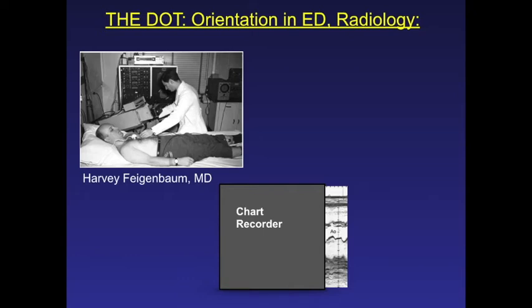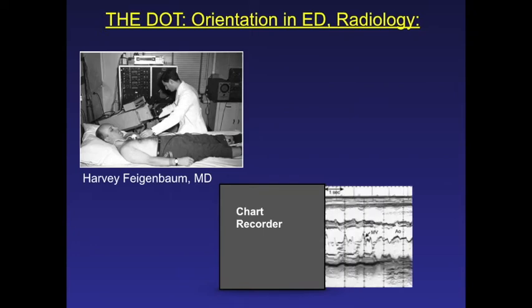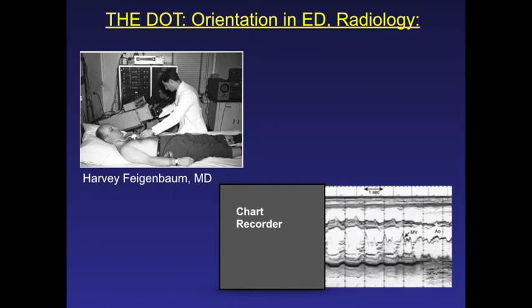Now, an M mode of the heart is one single beam, one scan line from one crystal on a transducer. And what they had to do is simply create what was called an M mode. M was for motion, because since it's only one beam, it was able to interrogate one region very quickly, because it only had to wait for one beam to come back to the transducer, not 128. And for that reason, even today we do M mode when we want to see something that's moving quickly and characterize its motion, such as the valves opening and closing.